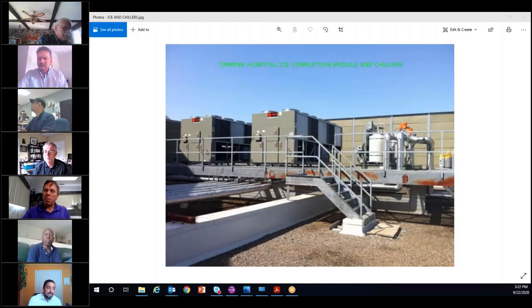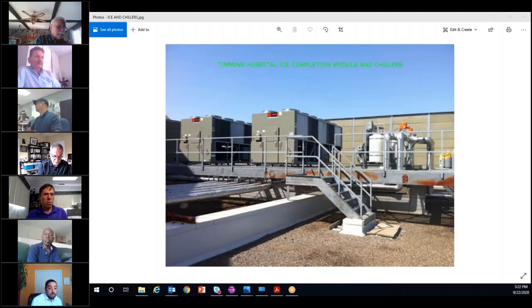They wanted to maintain some redundancy, at least a reasonable amount, but within reason, and obviously balancing out operating costs as well. They wanted to take advantage of some very lucrative hydro incentives at the time. That was when there was a utility incentive through Hydro One that was $800 per peak kilowatt of demand reduction, which obviously can go a long way if you can tap into that. So that got everyone very interested. And of course, as any customers, any hospital, or anyone who operates a building can attest to, they wanted to reduce maintenance costs as well as reduce their operating costs as a result of the energy usage of this system.